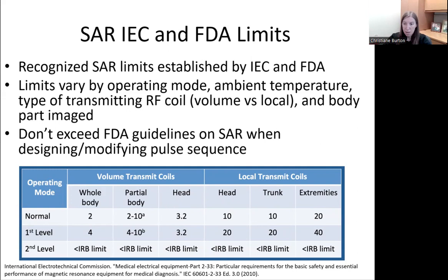The FDA requires equipment operating in this mode to display and record the SAR levels and display a warning that the first level mode is about to be reached. The MR scan operator must acknowledge this at the console before being allowed to proceed with the scan. The second level controlled operating mode is known as the research or experimental mode. This level is reached when an operation may produce significant risk to patients. Second level mode may only be used under an appropriate ethics or human studies protocol. Special security measures such as software password lock must be used to prevent unauthorized operation in this mode.